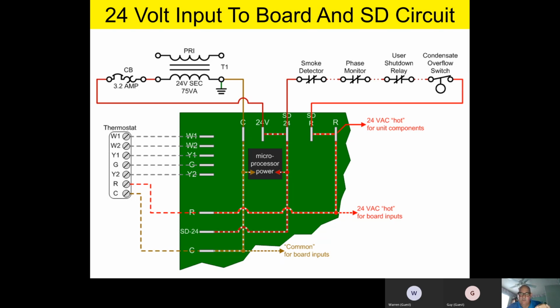So that SD24 and SDR circuitry, that safety circuit, you pull that jumper off, put whatever you want in there as long as they're dry, click, click, normally closed relay contacts. Any questions or comments on that little circuitry real quick before we move on? No, we're good. Okay, good, excellent.